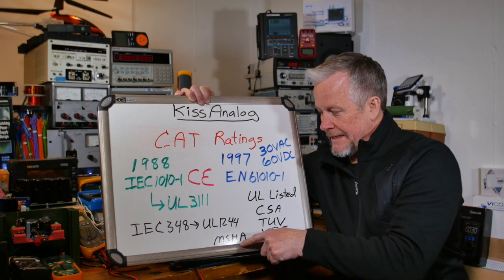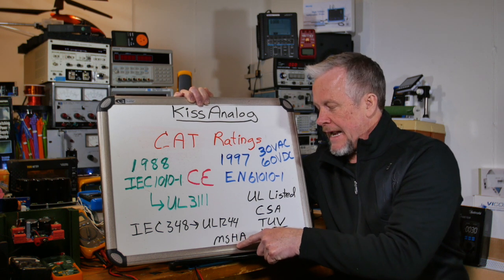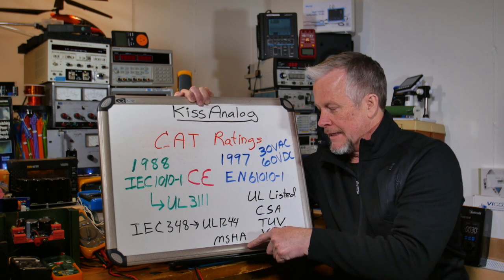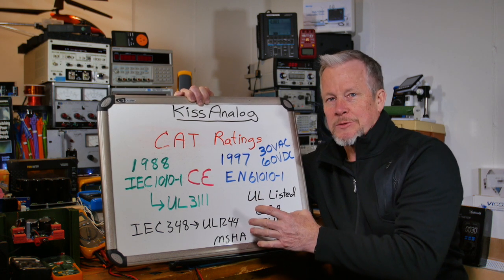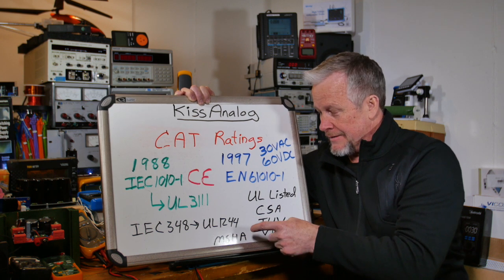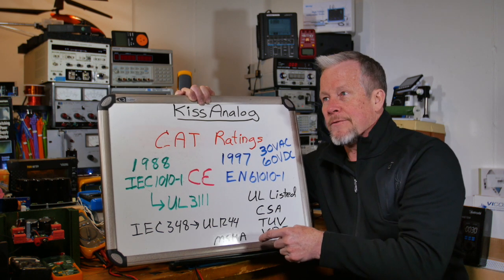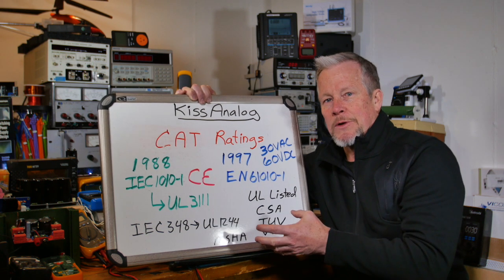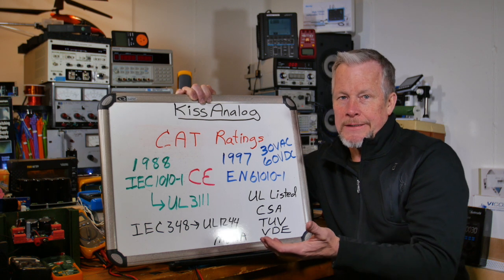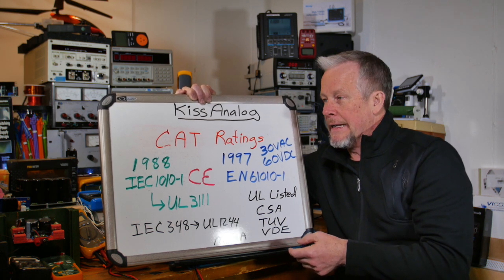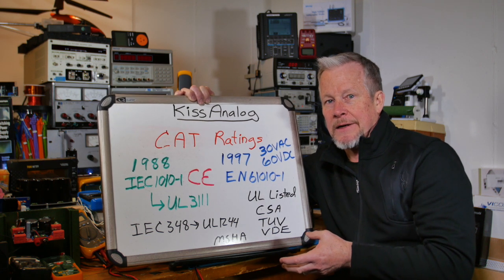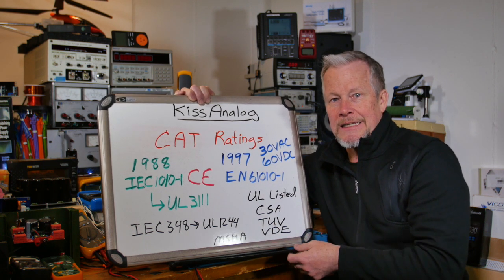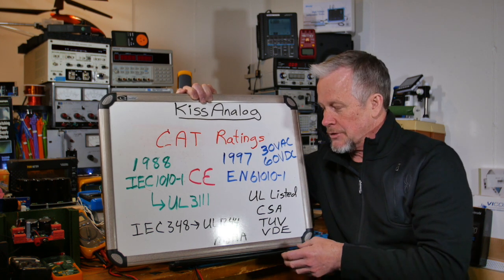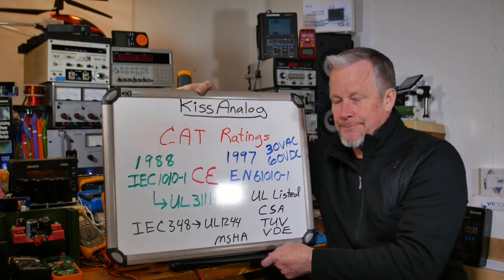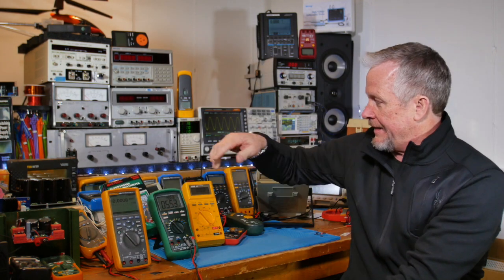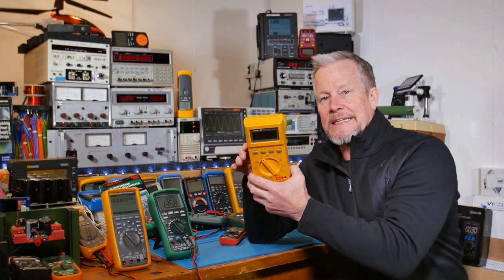And then there's another listing. This MSHA, that's Mine Safety Hazardous Agency, I think what it is. And by the way, this doesn't just apply to multimeters, but test equipment is what I believe that applies to. What MSHA means is you could be working around places where there's an explosive atmosphere. Mining industry, obviously, is where this came from. And if there's an arc or a spark inside that meter, it's not going to be exposed to that explosive atmosphere and really cause an explosion. So this guy here is kind of the ultimate as far as containing that arc blast or sparks and stuff. This guy has the MSHA on it.